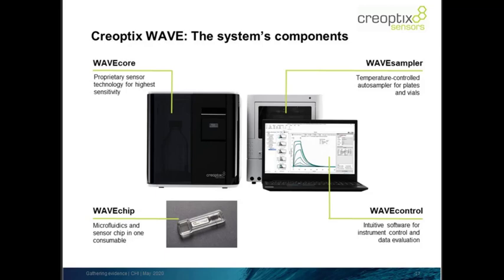Another question for Ellen: could you comment on using the Creoptix Wave for bispecifics and whether avidity effects are seen upon binding of individual antigens? Avidity effects for bispecifics can get tricky — it matters which portion is injected and whether we're talking about peptides, proteins, or a mix. One way to help is to push down the amount of protein immobilized on the surface, leveraging the instrument's sensitivity to minimize avidity effects on your measurements. Ultimately, some empirical experiments will still be required.